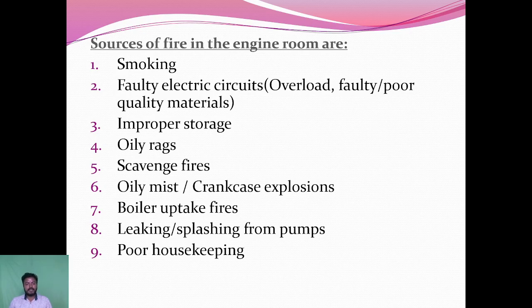Scavenge fire. In the engine room, in the main engine, there is a scavenge space area that is supplied with air from the turbocharger. In that area, some carbon may be deposited if there is no proper cleaning. That collection of carbon and fuel continuously collects, ignites and becomes a scavenge fire.